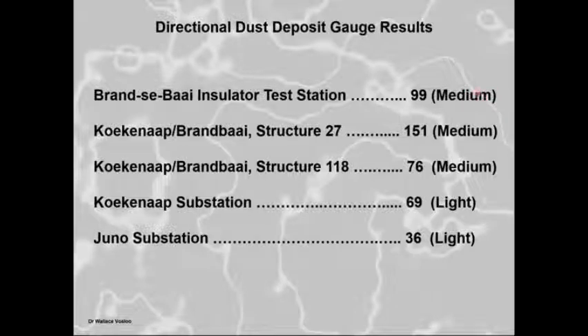That's medium. That is like a kilometer from the coast, and that is typically where some flashovers were found, and that is medium. I mean, medium in a marine environment is telling me that actually it's not bad at all, okay? And then at structure 27, where there was a flashover, we put up a dust gauge and we also got medium. Then at another structure where we had a flashover, we also measured medium. And at the substation, remember that substation where the glass stops or is light, and the substation where the glass starts is also light. So where the glass is, it's light, and where the composite is, it's medium.